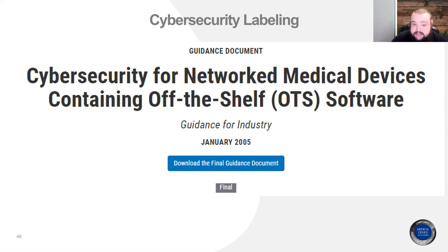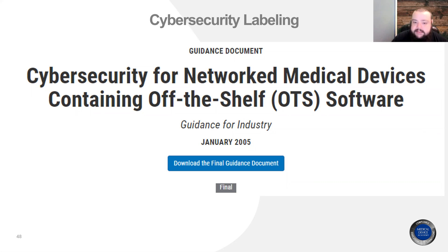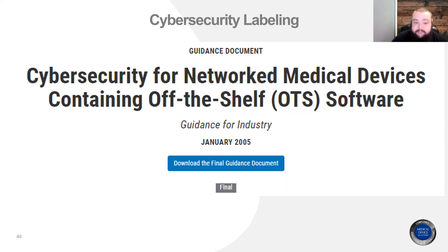The FDA also offers a guidance document on cybersecurity for networked medical devices containing off-the-shelf software. What I've seen with this is software components of devices that are both hardware and software — not always software explicitly designed for a medical device. This will help you tie in your software of unknown provenance to the design of your device. Unfortunately, it's even more outdated than the content of pre-market submissions — it's from 2005 — but it's the most up-to-date guidance the FDA has released.